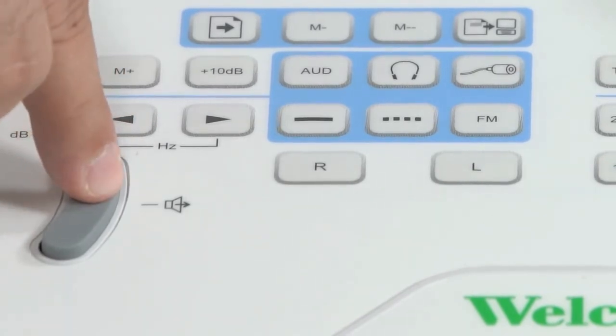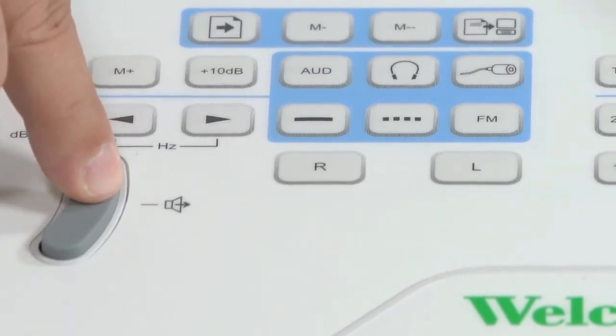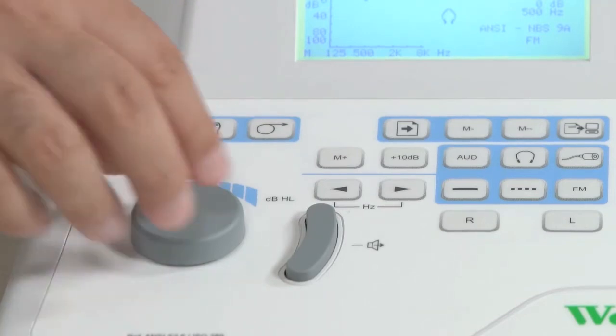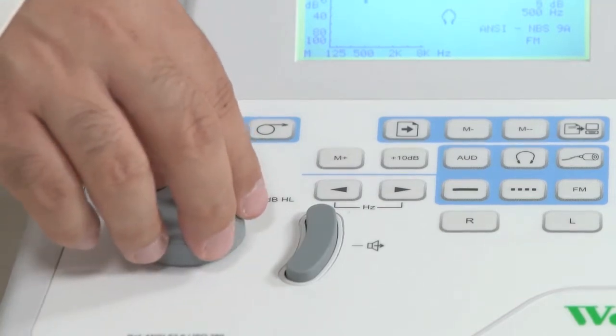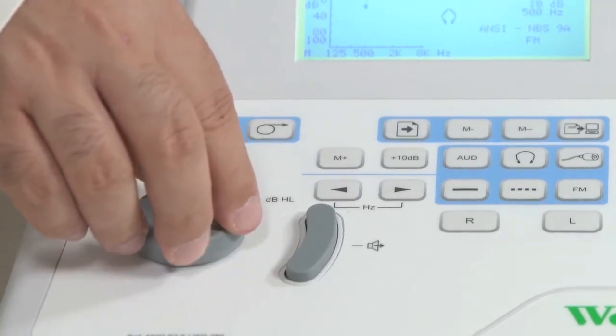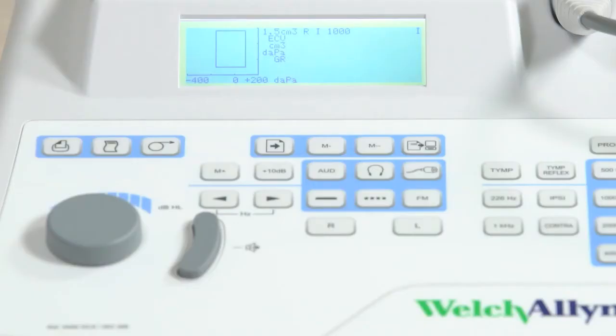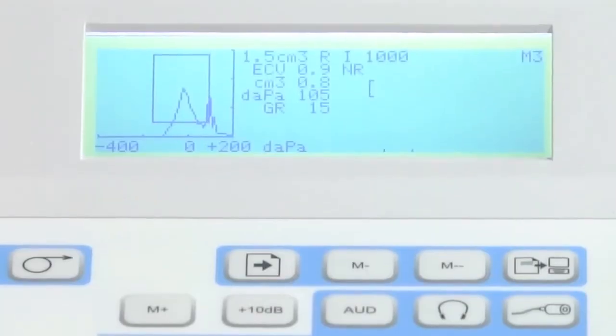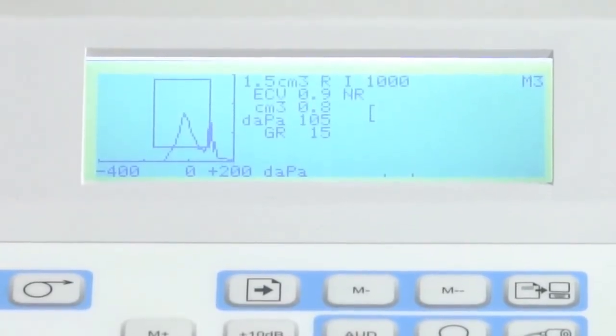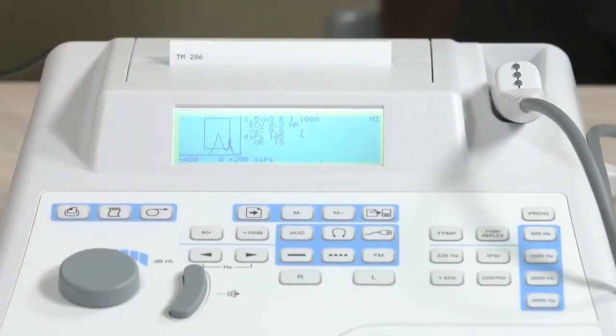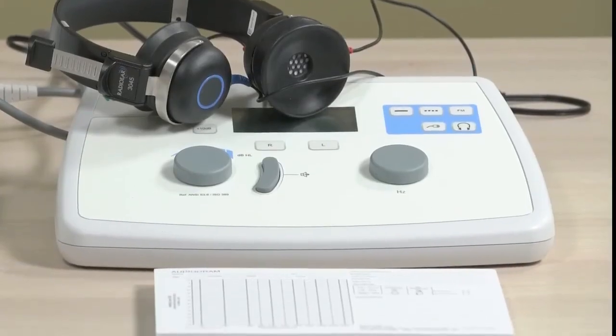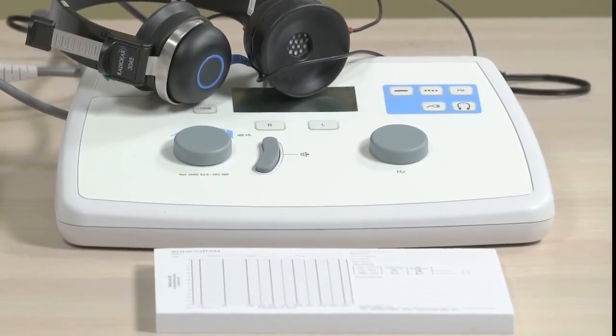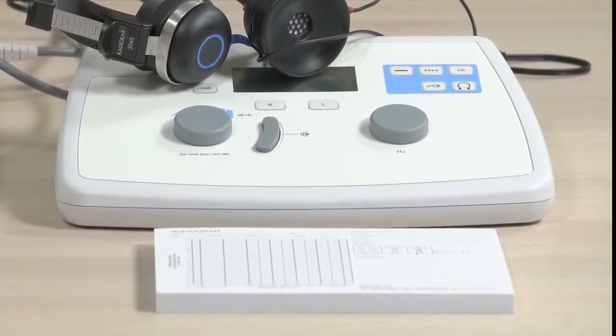The presentation button should be held for 1 to 1.5 seconds. The HL knob increases or decreases the signal intensity in 5 decibel increments. When the maximum or minimum available intensity is reached for any frequency, the display will flash. With the TM286, results display on screen and can be printed. With the AM282, make whatever notations your procedure requires on the provided audiogram forms.